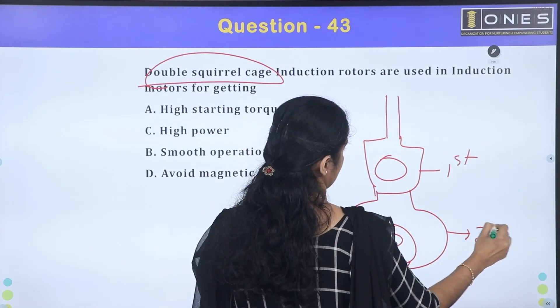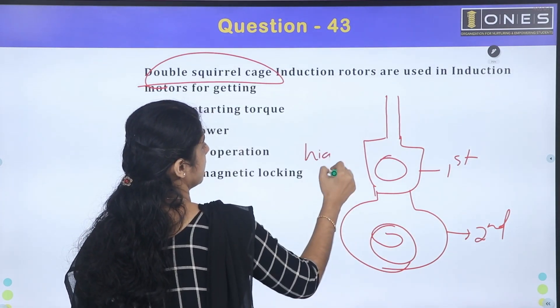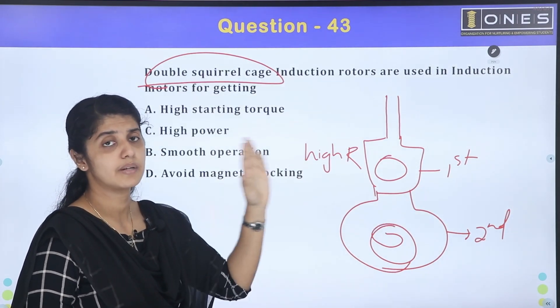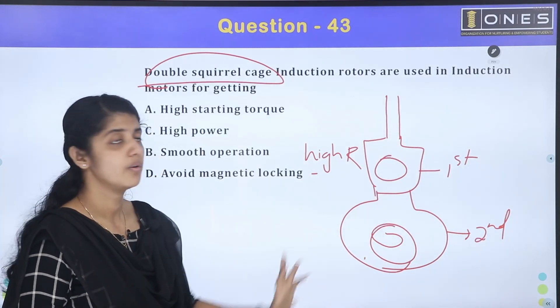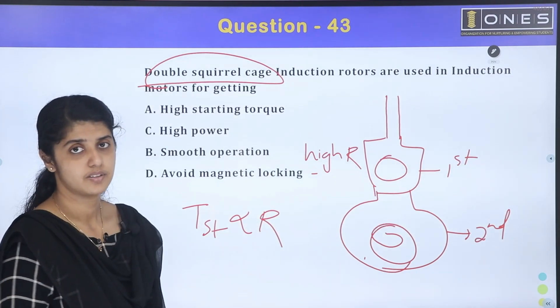In the double squirrel cage motor, the outer cage has high resistance and the inner cage has low resistance. The outer cage provides high starting torque while the inner cage carries the main load current during running conditions.